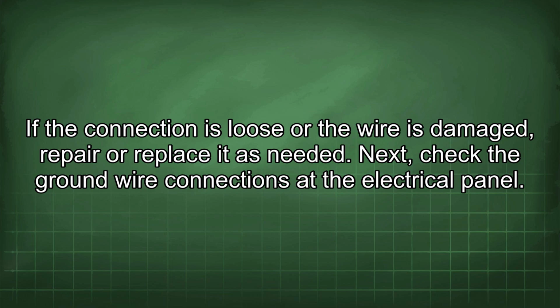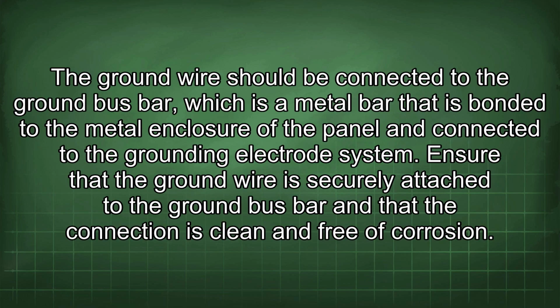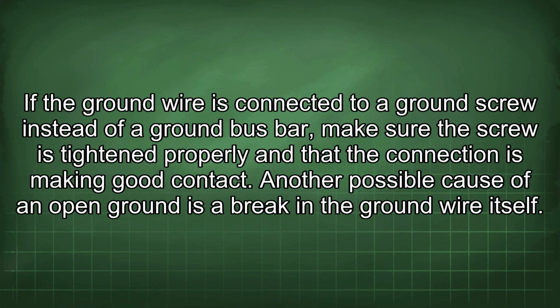Next, check the ground wire connections at the electrical panel. The ground wire should be connected to the ground bus bar, which is a metal bar that is bonded to the metal enclosure of the panel and connected to the grounding electrode system. Ensure that the ground wire is securely attached to the ground bus bar and that the connection is clean and free of corrosion. If the ground wire is connected to a ground screw instead of a ground bus bar, make sure the screw is tightened properly and that the connection is making good contact.